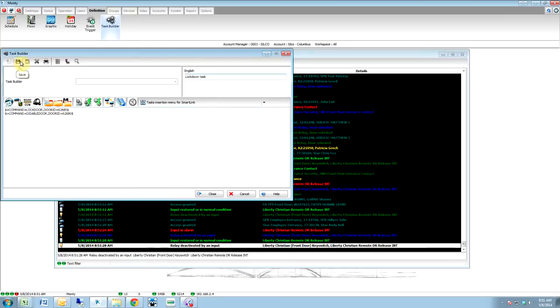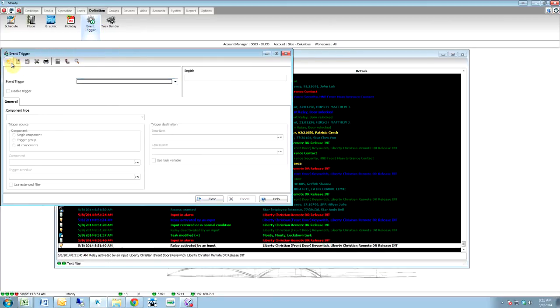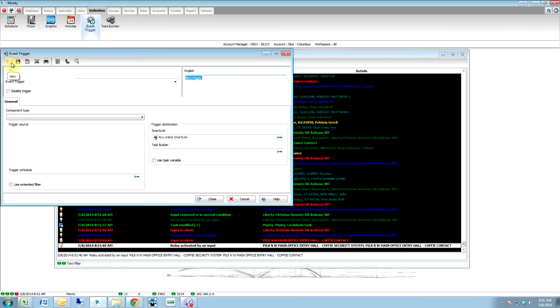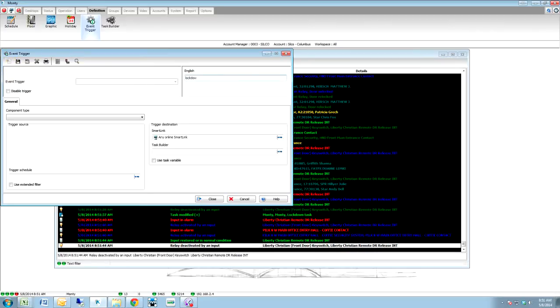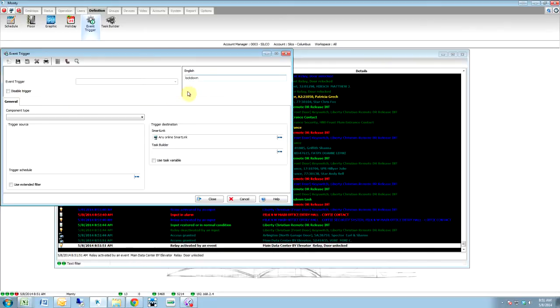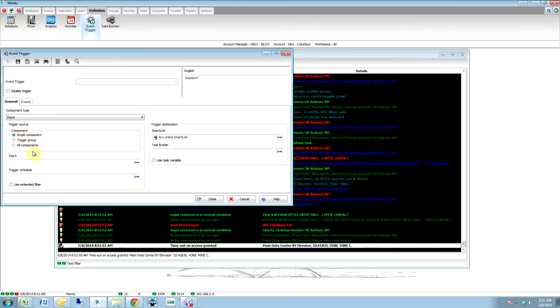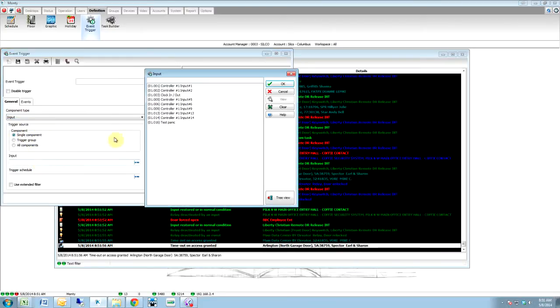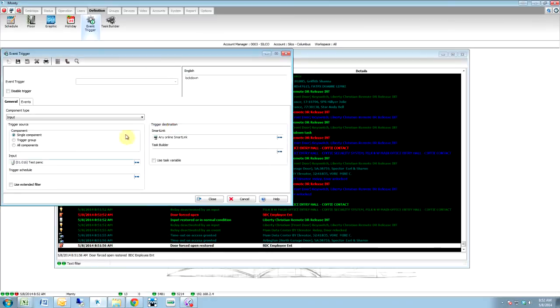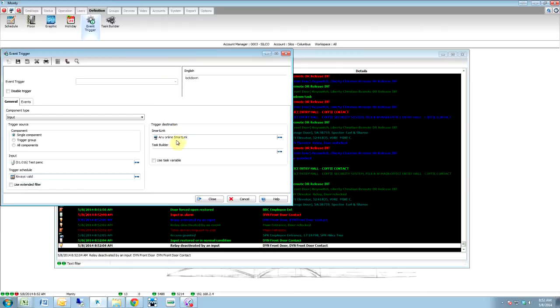So now that we've got our task, we're going to save it. We're going to go to our event trigger. We're going to make a new event trigger, and this is going to be Lockdown. Then in the Lockdown, we're going to go to component type, we're going to select an input — a single — we're going to select our input we just created, the test panic. And then we're going to watch it all the time.